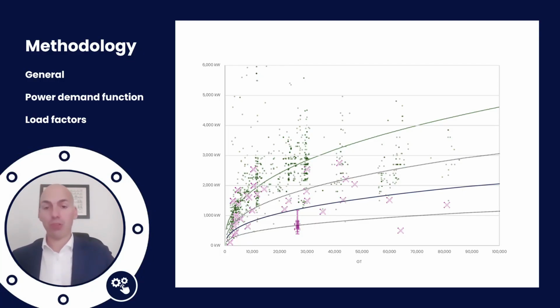But if you look at the real-time measured data, which are all for the same ship type, a few, you can see that they're actually closer to the low band, so our low estimate. And the high one, well, if you look at making a business case, I wouldn't go there, because that means that if you are looking for a shore perspective, you're making a lot of money because you're selling more kilowatt hours. I would suggest going maybe to the low band for the low cases and just the average band to get a base case. But those are the load factors that we do.